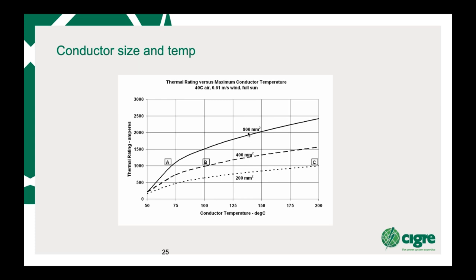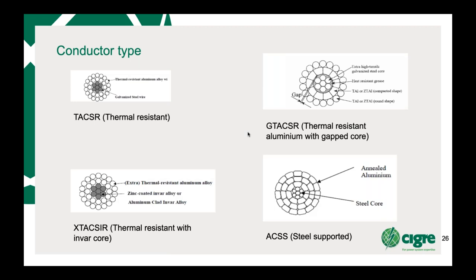So this is quite important, that you need to understand what the planner really requires in relation to the particular load and when that load is going to occur. Is it 1 hour per year, 1 hour per 2 years? Is it only going to happen once in the life of the line, or is it going to be continuous? This is very important. Looking at the different conductors that you can actually start considering, there are many, many kinds, and these are just a couple.